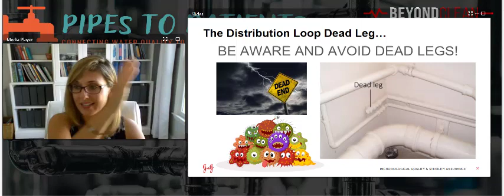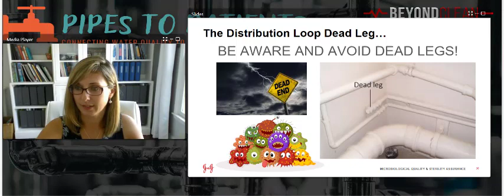And biofilms are not predictable, meaning you might do your monitoring and today you get a huge amount of microbial detection, and tomorrow you'll get nothing, because it's based on when they slough off and the top layer moves so the bottom layer can move up. Just like in our communities, how we move in and out of cities, that's the way a biofilm moves. So it's really important that once you identify dead legs within your system, you work cross-functionally within your multidisciplinary team to address these, because just because your indicator says you're in control doesn't mean that tomorrow you won't be.